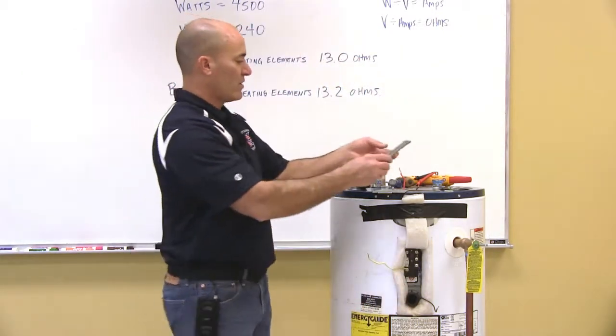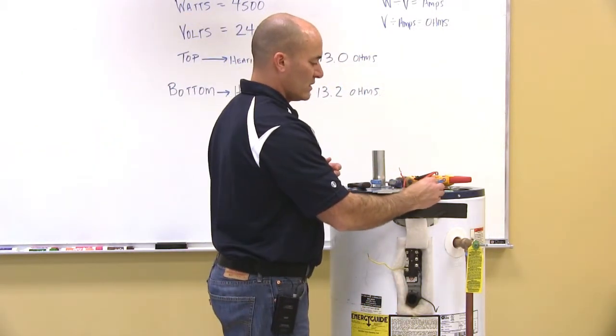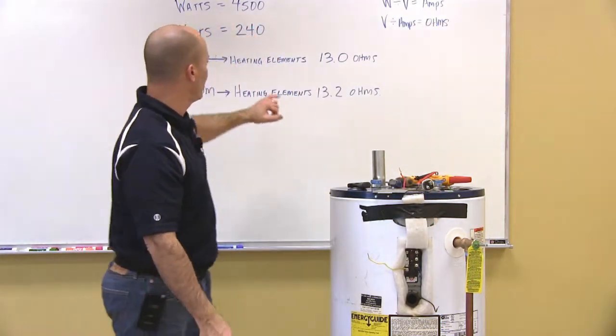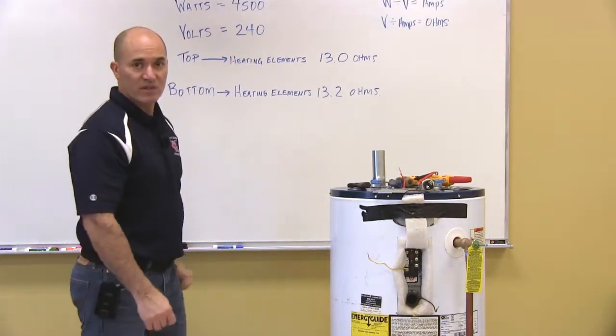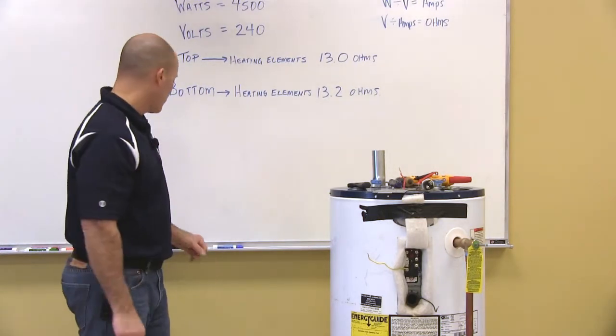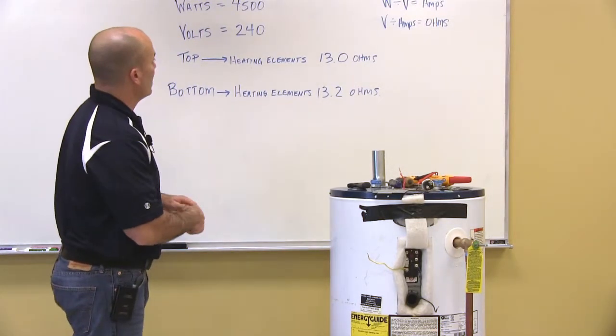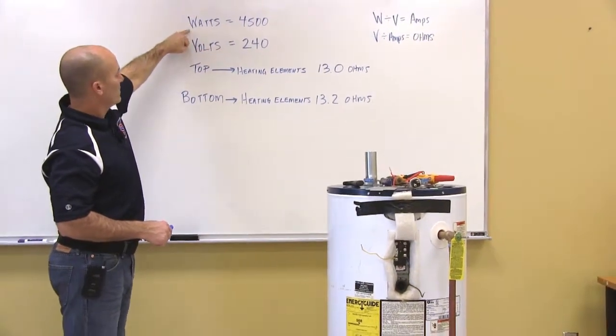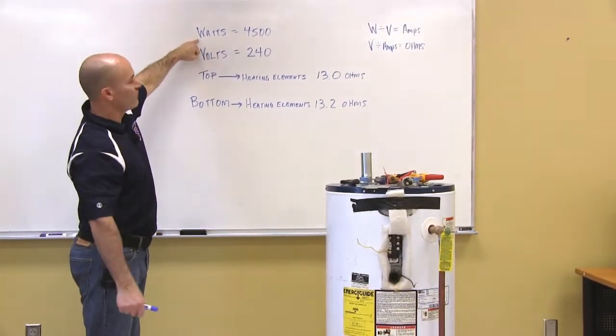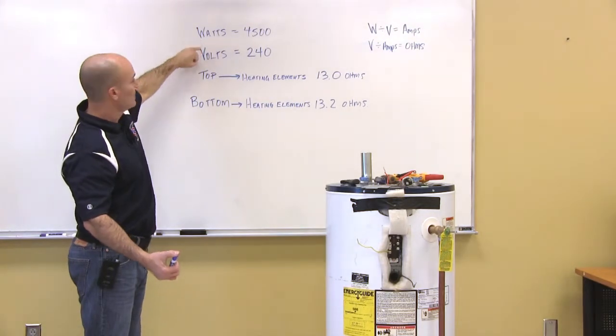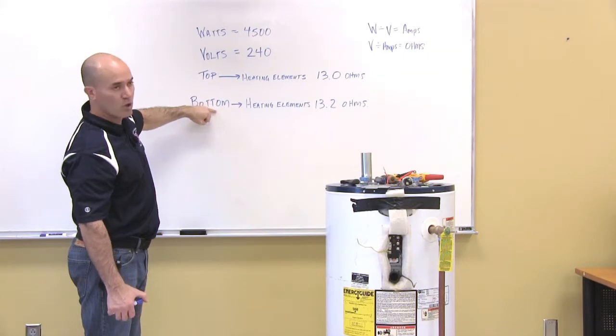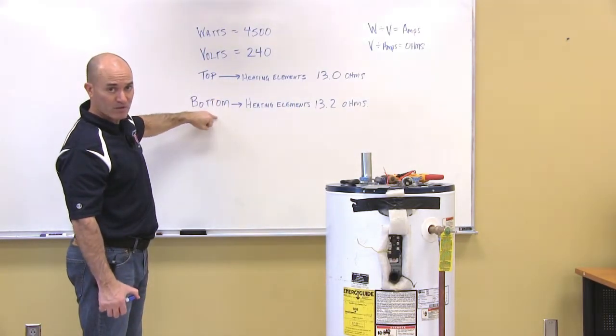So now, what I'm going to do is, I looked at this, I've already tested it, this is the top heating element, it was at 13.0. So I've written all the figures down here for you. We looked at the plate on the tank, it was 4500 connected watts, voltage was 240, and we tested for our ohms reading on both of our heating elements.